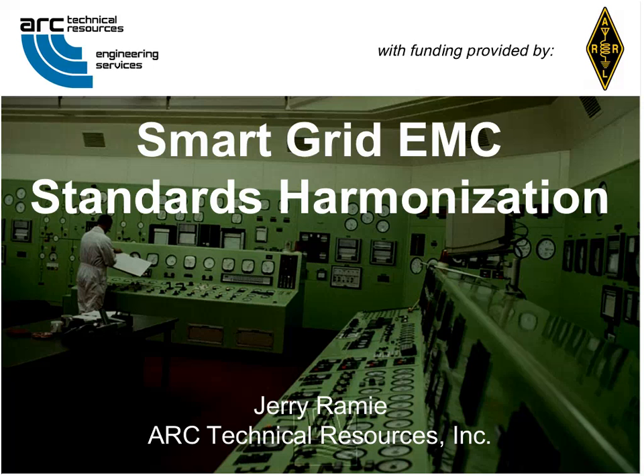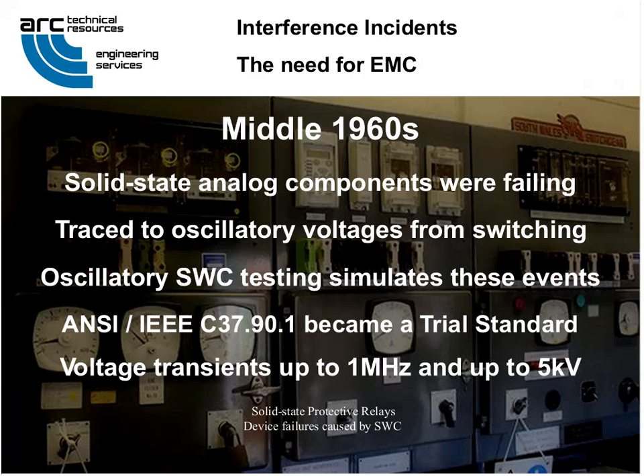So with that, I'm going to give you some examples of the need for this kind of work that goes back many years. In the mid-1960s, the new solid-state analog components in protective relays were failing in utility electric substations. Failures were traced to oscillating voltages created from normal switching operations, not high current faults. The oscillatory surge withstand capability, or SWC test, simulates those events and was first codified in the mid-1970s as ANSI IEEE C37.90.1, then a trial use standard.